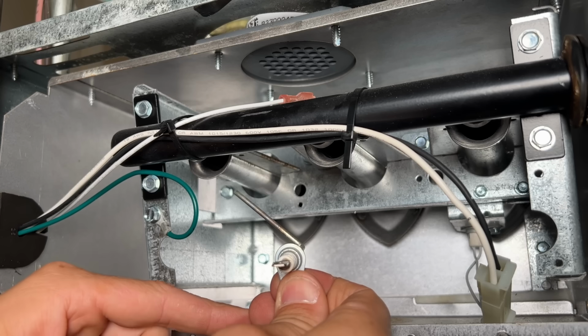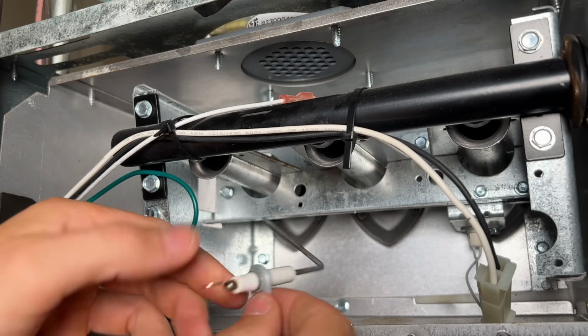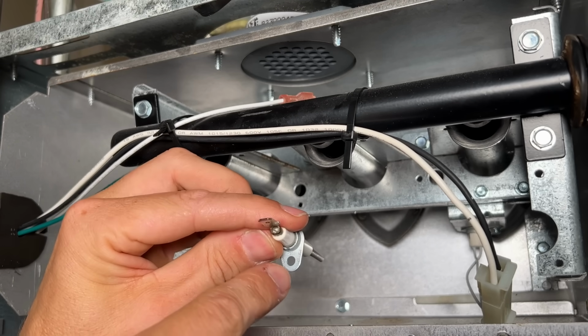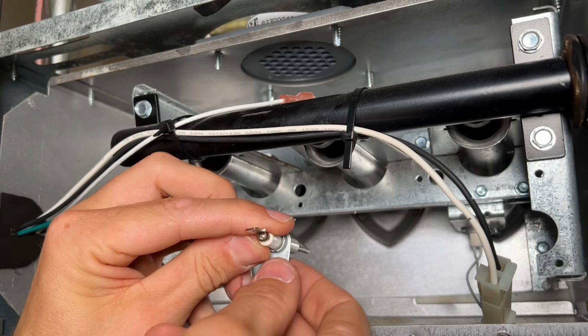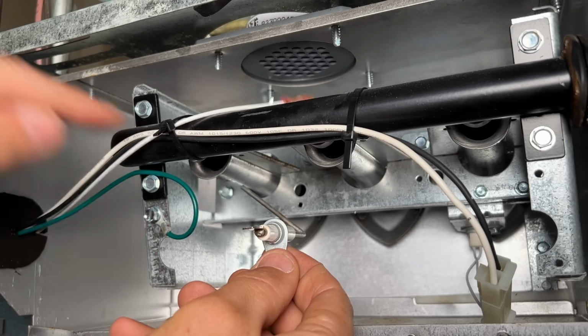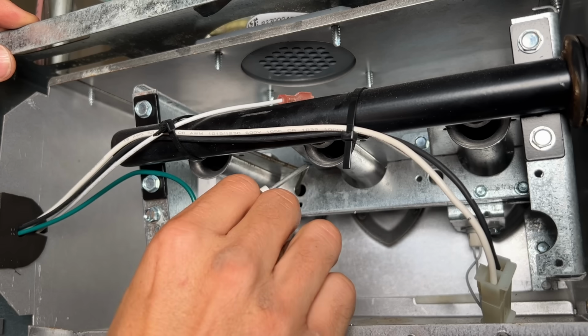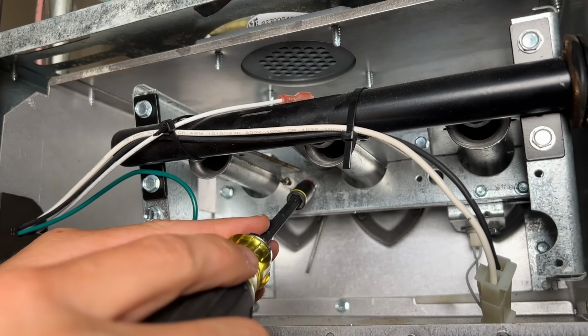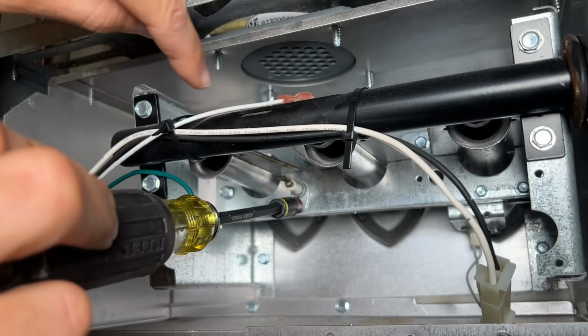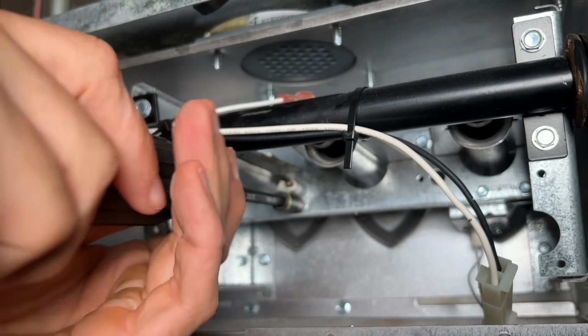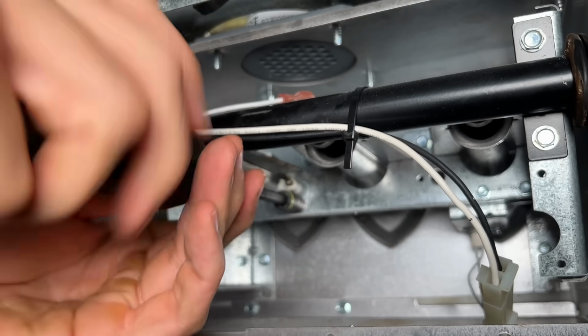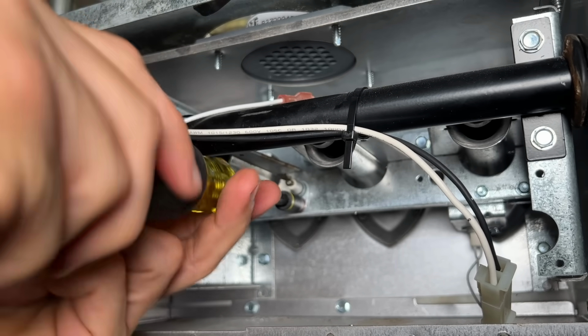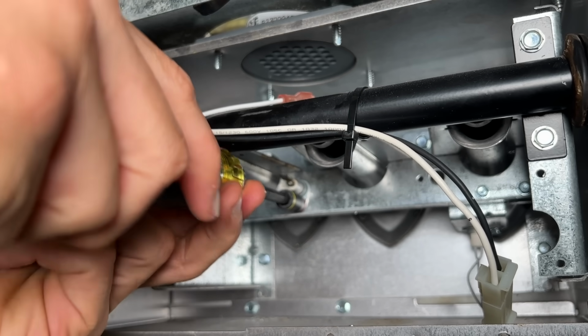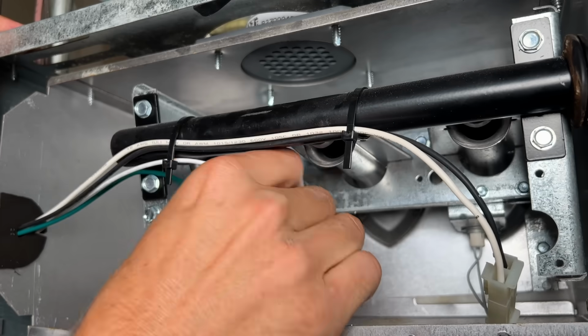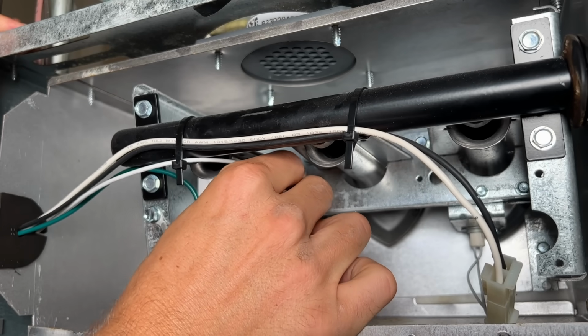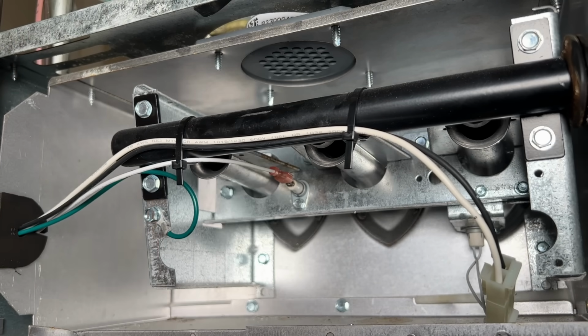Basically, you want to get the same orientation, whether you have a straight rod, or you have a 90-degree like this, but then pay attention to where that mounting hole is for the screw, because that's really going to be the thing that orients that rod into the path of your flame. And that's the key. It has to be in the path of your flame. So for me, when this is fully mounted, that rod is pointing towards the last burner there, and that would be critical. You don't want to get a flame detection sensor that is going to position that rod in the middle of the burners, and it's not going to work effectively.